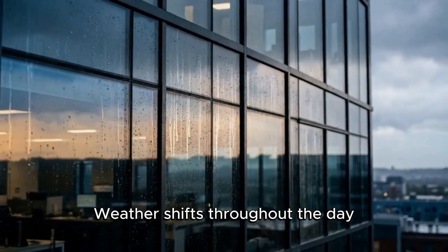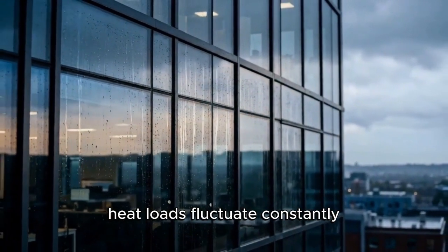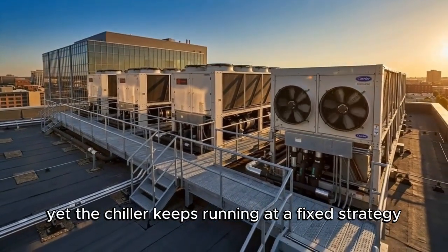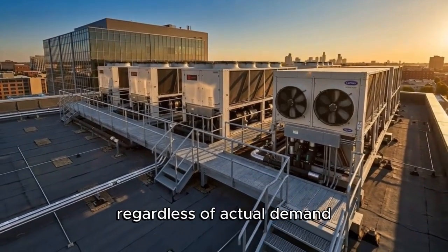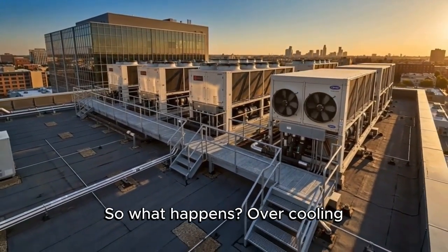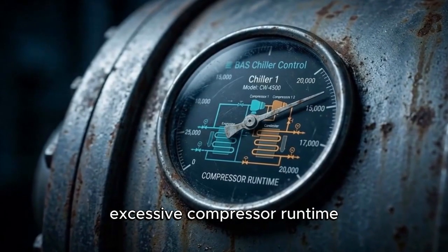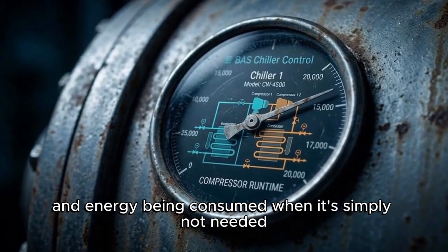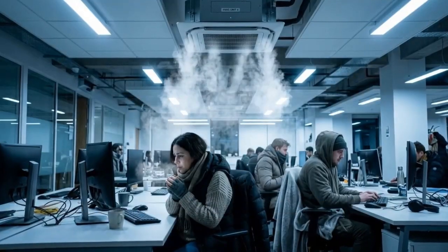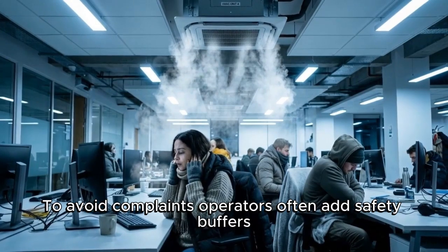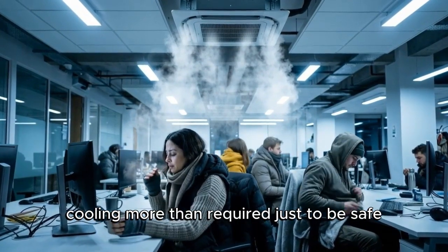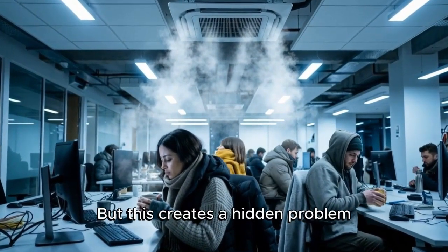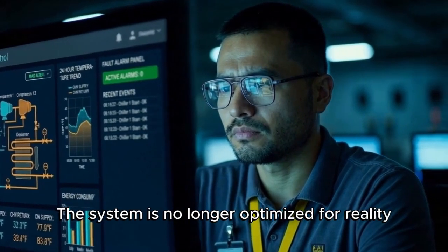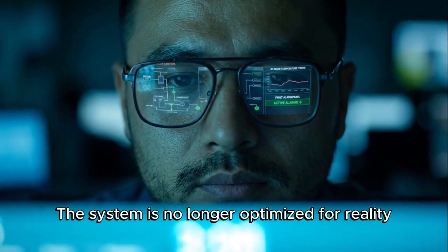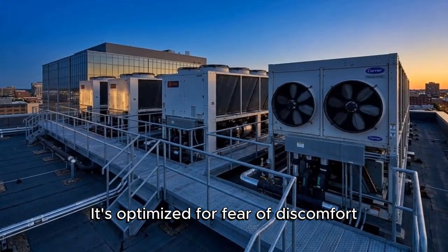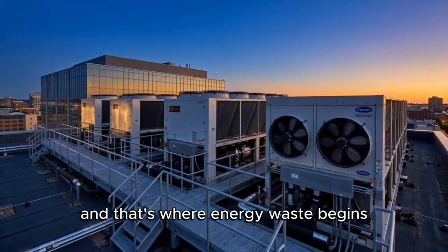Weather shifts throughout the day. Heat loads fluctuate constantly, yet the chiller keeps running at a fixed strategy, regardless of actual demand. So what happens? Overcooling, excessive compressor runtime, and energy being consumed when it's simply not needed. To avoid complaints, operators often add safety buffers, cooling more than required, just to be safe. But this creates a hidden problem. The system is no longer optimized for reality, it's optimized for fear of discomfort, and that's where energy waste begins.